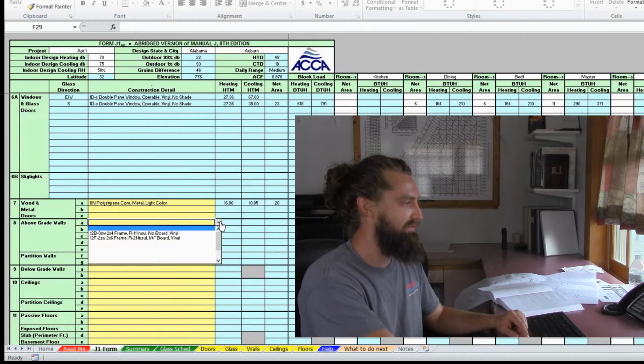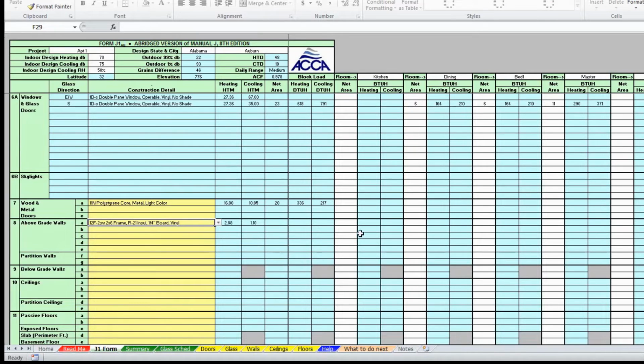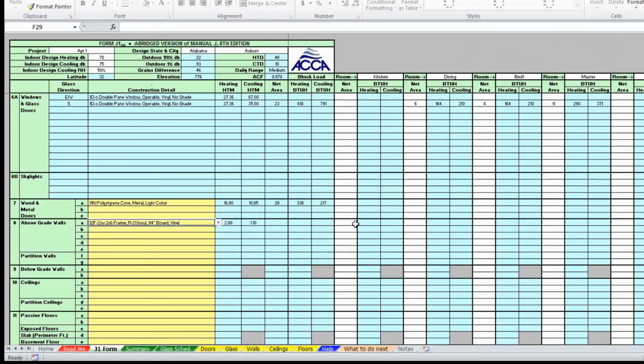Above grade walls: we are going to choose the 2x6. This is where you'd look at your blueprints or notes, and start dividing rooms up. It's easy to divide rooms when they're legitimate rooms, but it gets more difficult with open concept floor plans, where you have to determine if a wall is part of this room or that room, and how to chop it all up. Remember when I was looking at that apartment, our living room, kitchen, and dining room were one big area, but we have to mentally chop it into sub-zones, one for determining loads in each area, and another for determining what ductwork and airflow we need in each one.